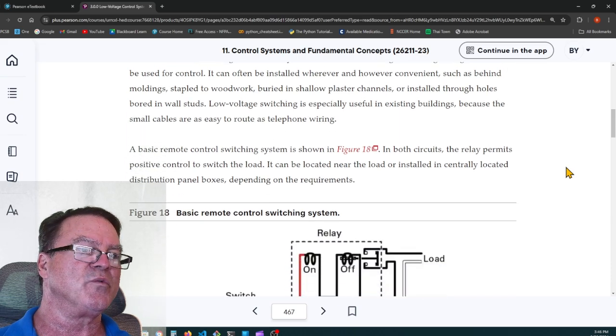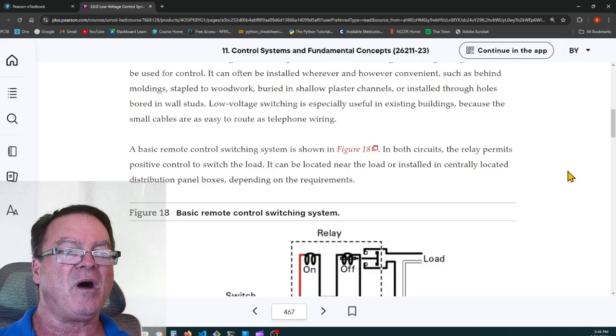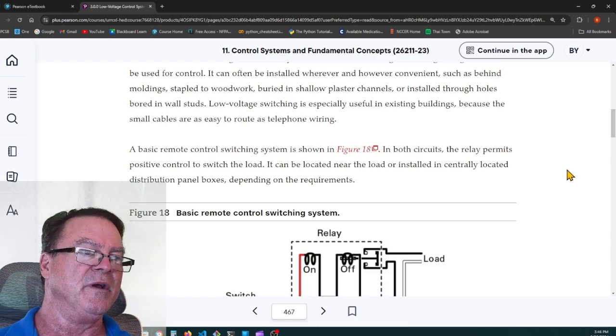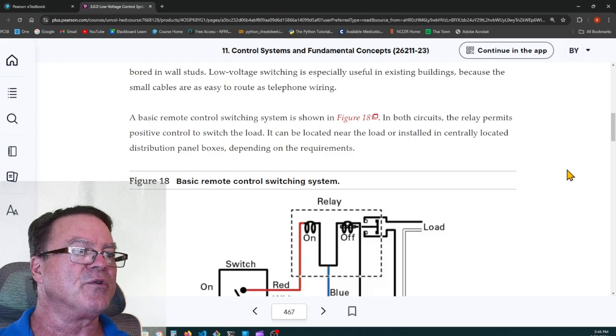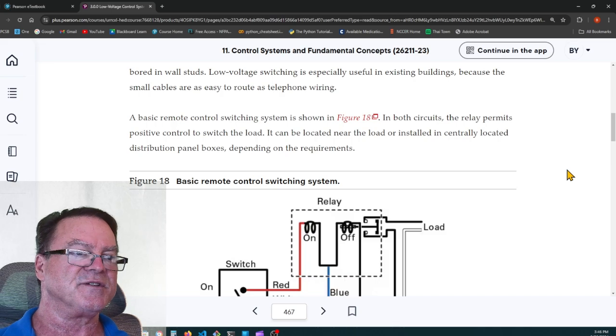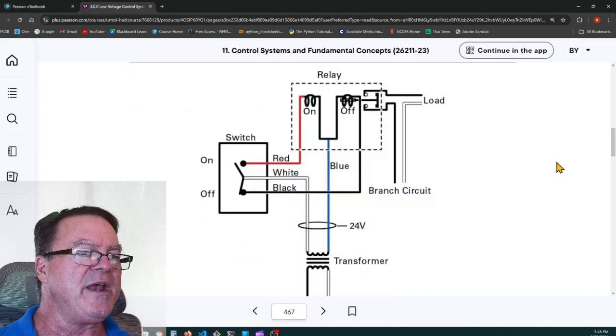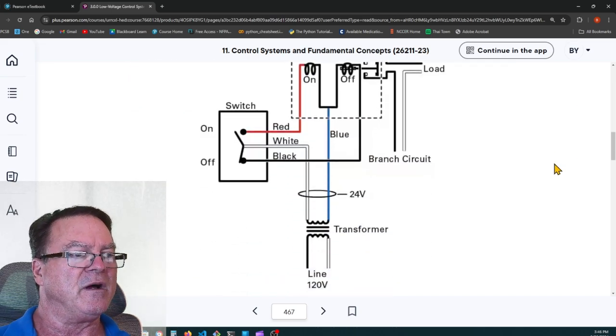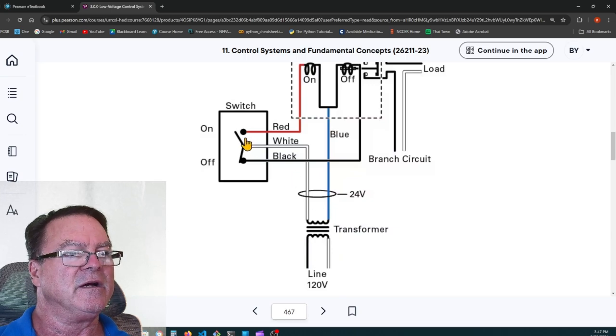Basic remote control switching system is shown in Figure 18. In both circuits, the relay permits positive control to switch the load. It can be located near the load or installed in centrally located distribution panel boxes, depending on the requirements. So here's a low voltage relay. Here's the switch, on or off.